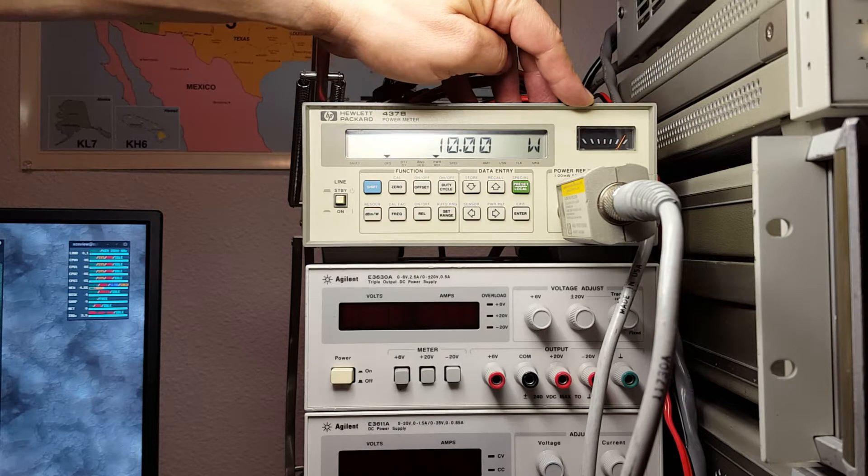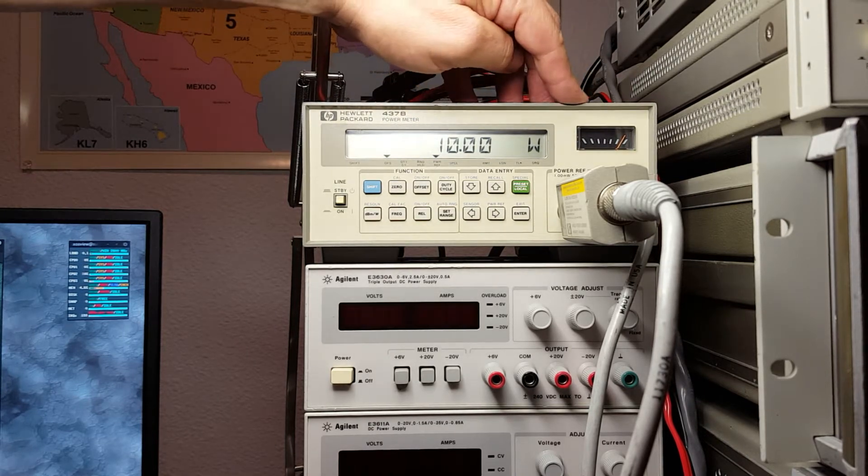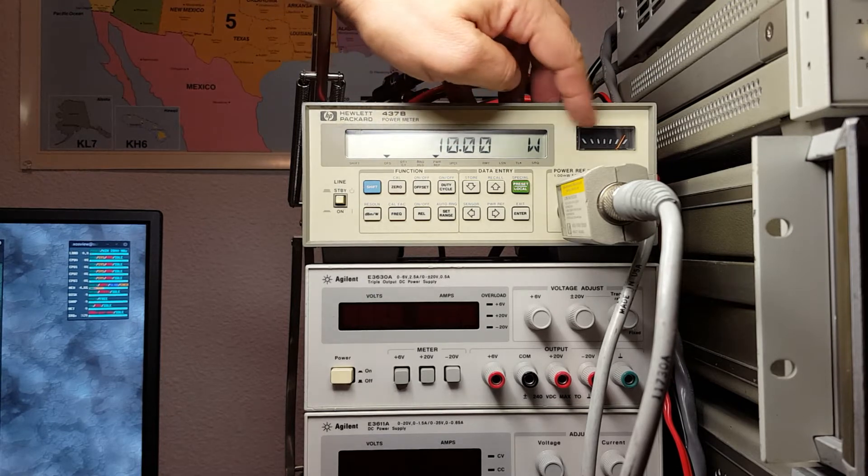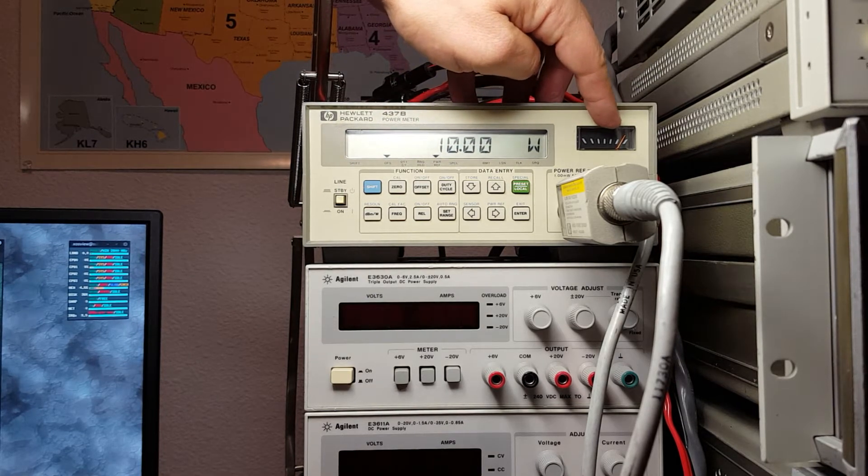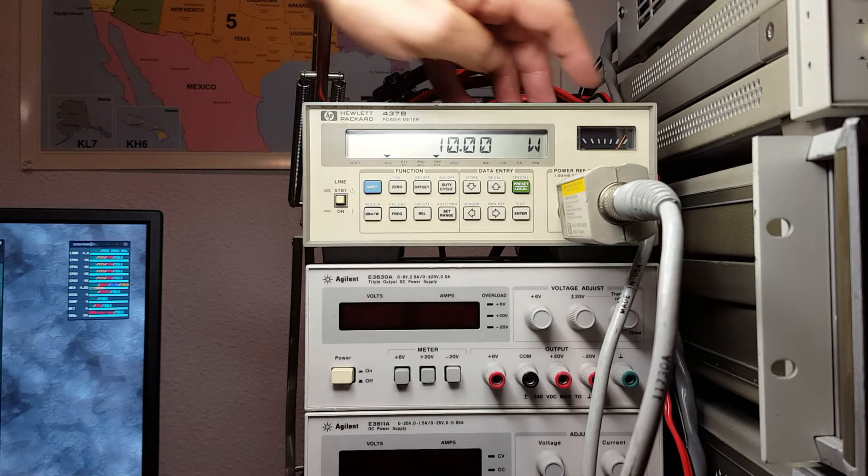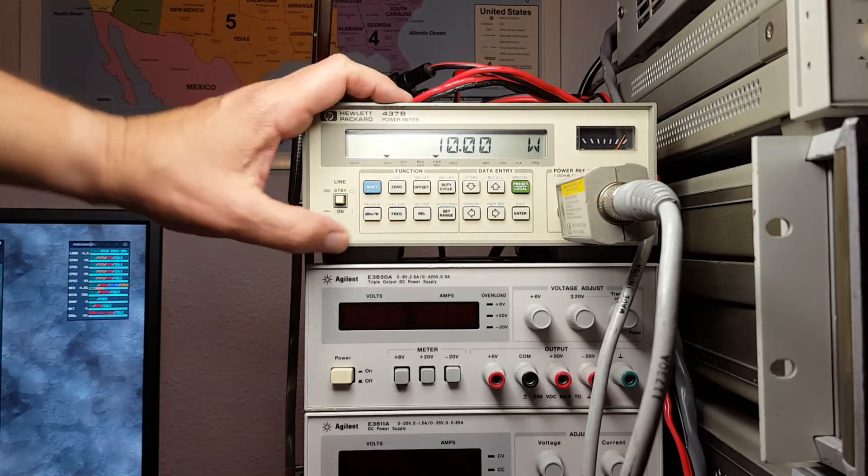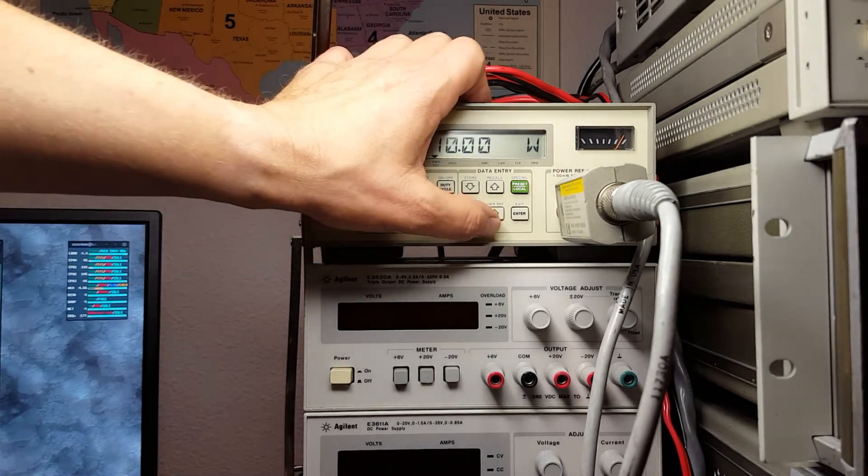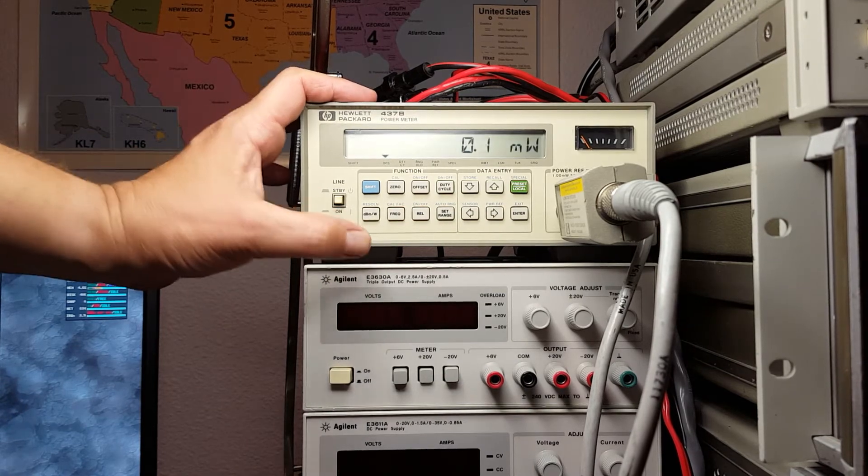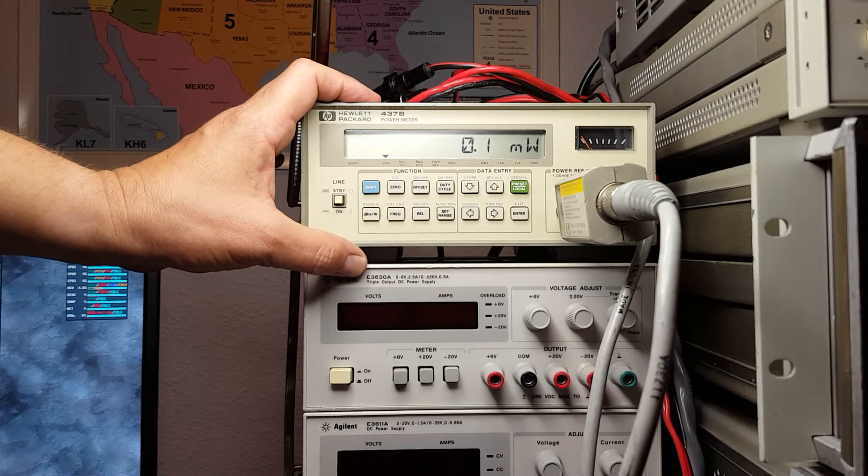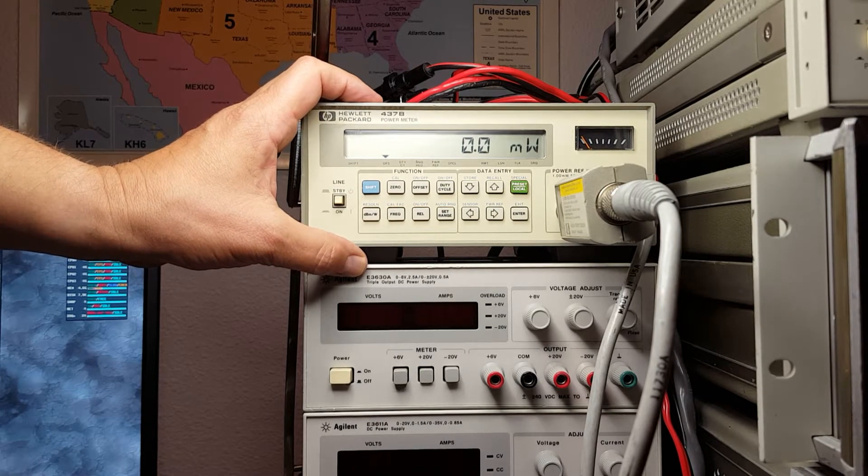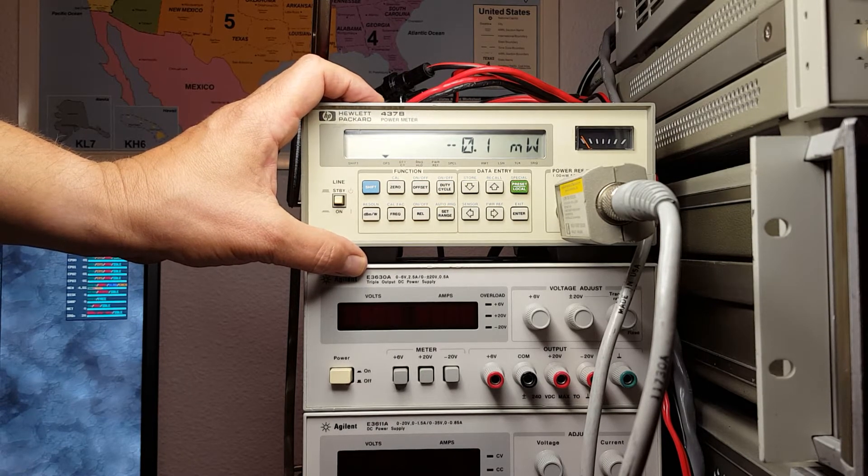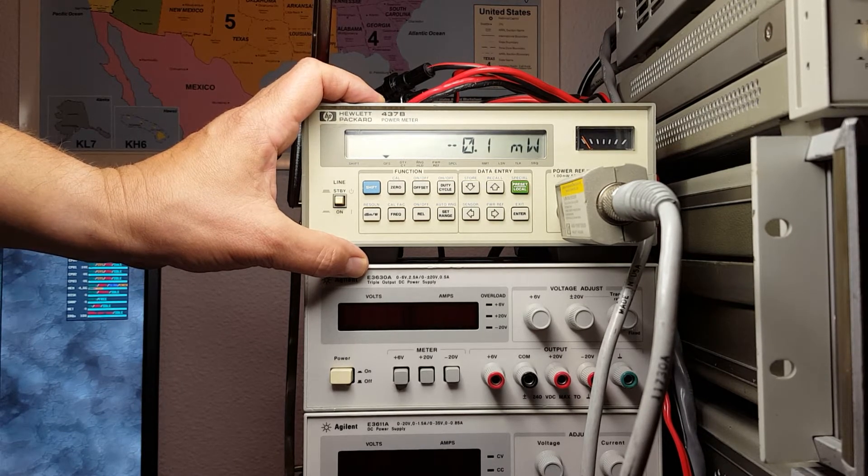The meter over here gives you a visual representation of where the meter is in the current range. This meter has five ranges and automatically selects. It also gives you the opportunity to see noise or to peak your readings, which you really can't do from the digital display. I pretty much use this for measuring references and calibration sources.